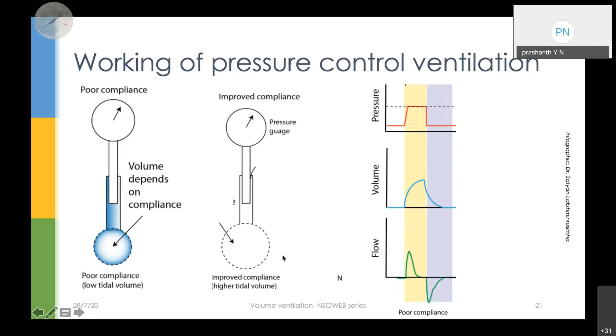So let's look at another scenario in pressure control ventilation where the lung is able to expand well. That is, the compliance is good. With the same pressure, we are able to push more air in. This is an example of improved compliance. Here the volume which is going inside the lung reflects the compliance. With the same pressure we are pushing more air because the compliance has increased. In the graph, you see my pressure has not changed, but look at the volume scalar here. The volume has increased for the same amount of pressure. This has happened because the compliance has improved.